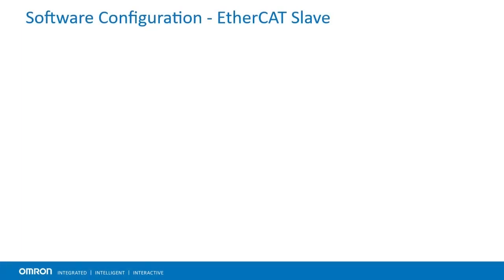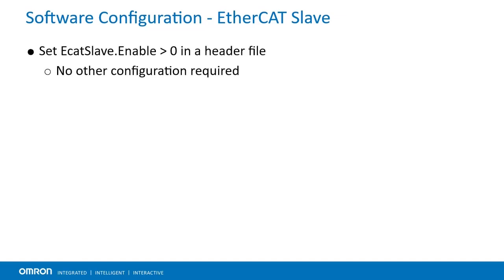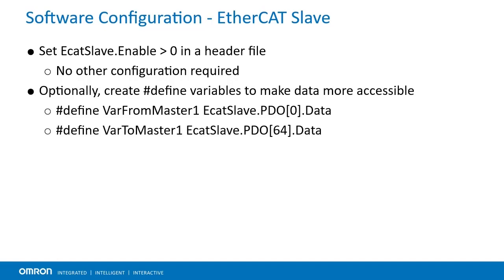Configuring the EtherCAT Slave is very simple. All a user must do is set ECATSlave.enable equal to 1, 2, or 3, depending on which clock they want to use. It is recommended to do this in a header file, then download and save it to the PMAC so the device automatically enables EtherCAT Slave functionality on boot. While not necessary, it may be helpful to create pound-defined names for the EtherCAT parameters so you can give registers more helpful names. Remember, index 0 is your first index written by the master to the slave, and index 64 is your first index written by the slave to the master.